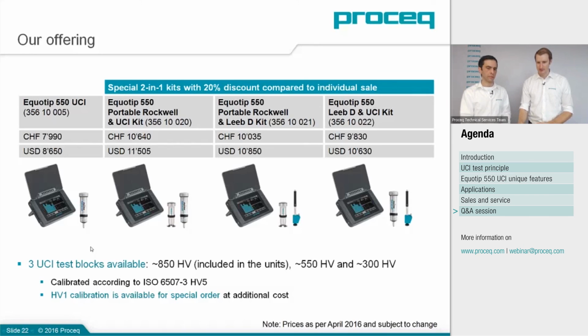The test blocks are calibrated according to the ISO standard for Vickers, and are calibrated in HV5. But we also offer additional HV1 calibration. If a customer is using his probe mainly with HV1, we recommend also having HV1 calibration on the test block. But the default calibration is HV5.